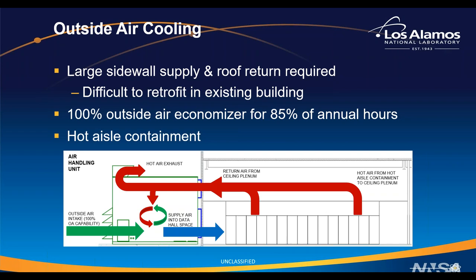In really cold temperatures, we can warm the air going into the data center in the wintertime, for example, by mixing some of the hot air exhaust in with the outside air. Or if it's really hot for a small percentage of our days, we can use warm water from the adiabatic dry coolers to slightly cool the air coming into the data center. It turns out we can use the outside air economizer for 85% of the annual hours. One thing to recognize with outside air cooling is that it's difficult to retrofit into an existing building due to the high air flows required.